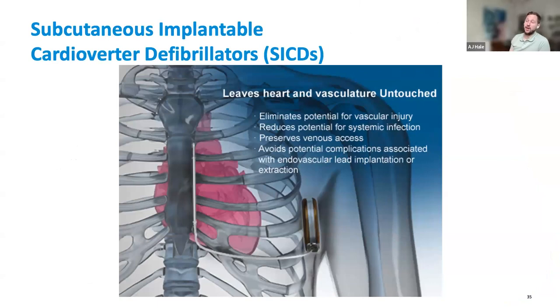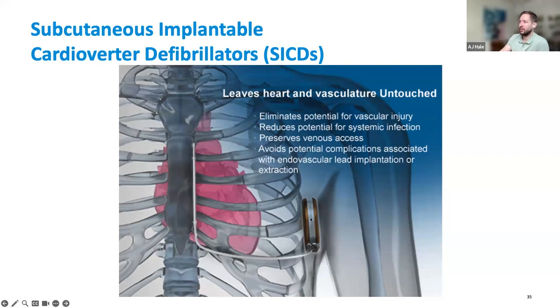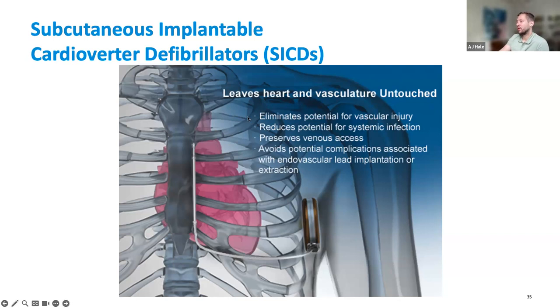We also have SICDs — subcutaneous ICDs. I've never worked with these before when I was at Abbott, and they still don't have a solution. Medtronic is coming out with one that is sub-xiphoid. The idea is that the lead is not transvenous — it's just underneath the skin, tunneled across, and the shock vector goes across the heart with the can underneath the arm. This eliminates the risk of vascular injury for patients with occlusion or higher infection risk. We saw these often in patients with drug issues, as it's good to avoid putting anything in the vasculature that could get infected, and it preserves venous access.